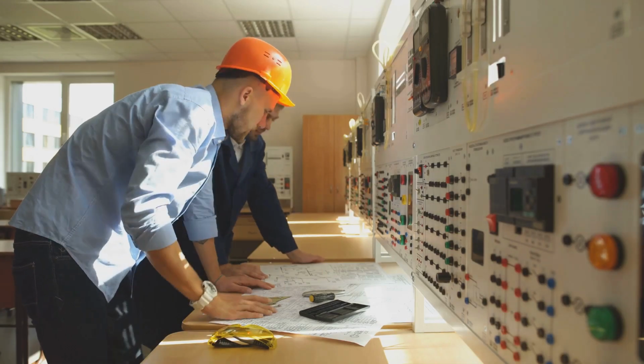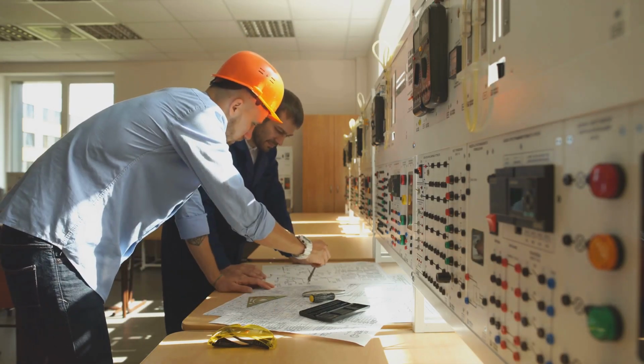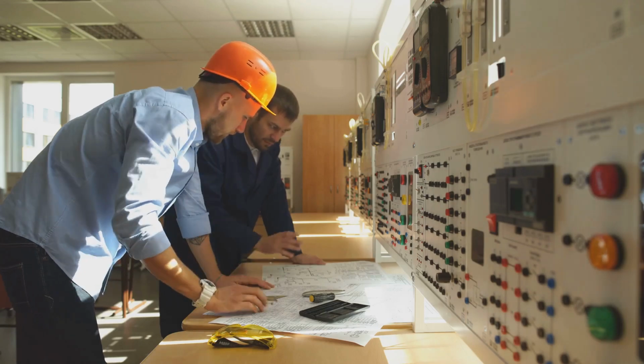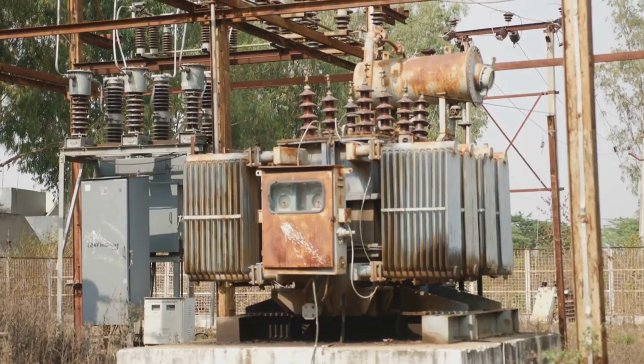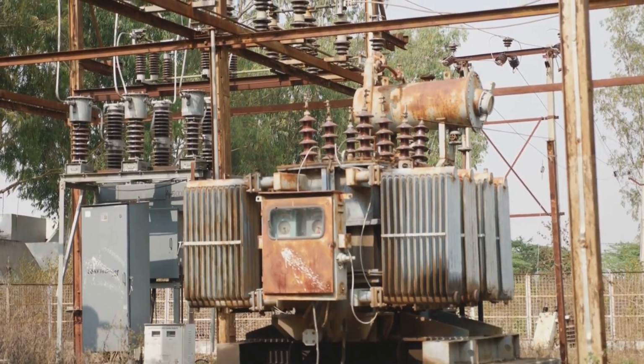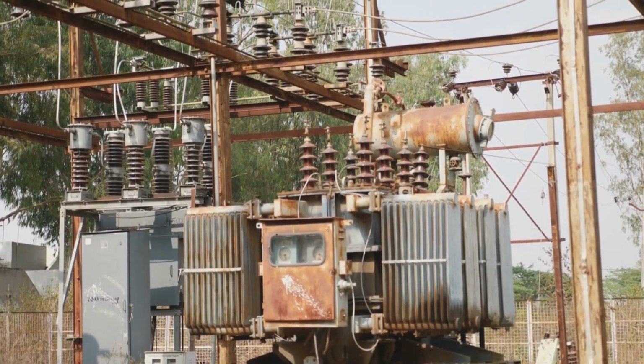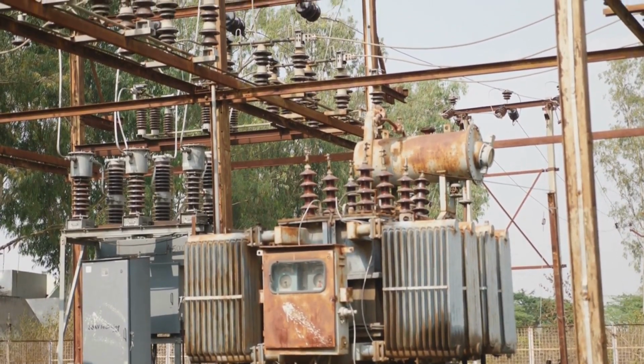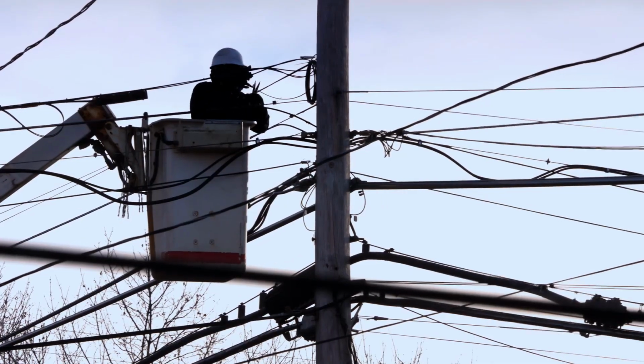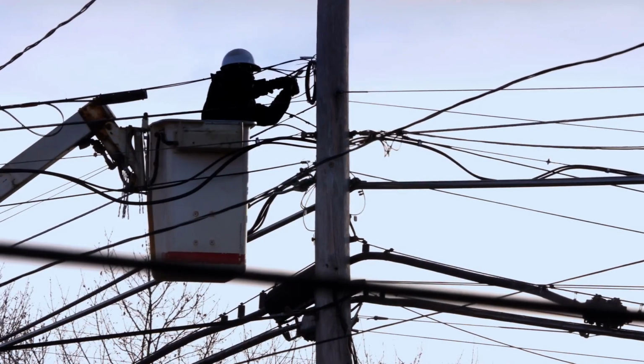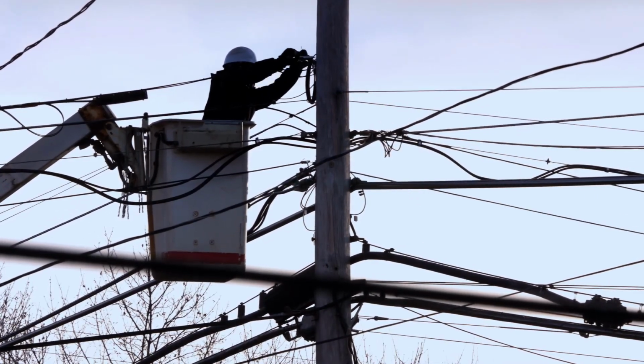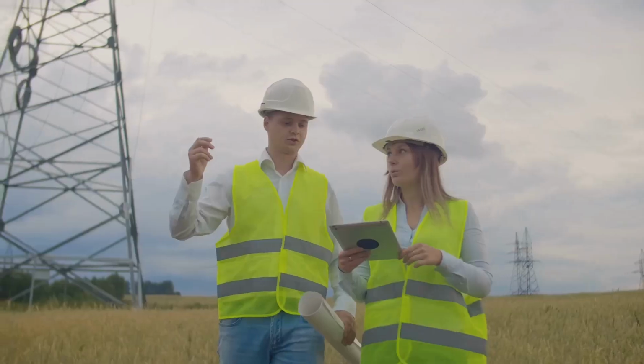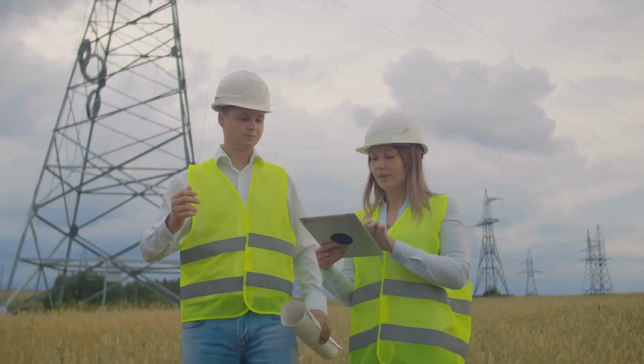IEEE 1547-2018 mandates that DERs must cease to energize an unintended island within 2 seconds. During a grid fault, especially if a recloser operates, there's a risk that a DER could become isolated while still producing power. This creates safety hazards for line workers, and risks damage to equipment operating without proper voltage or frequency regulation. From an FRT angle, this creates a paradox.